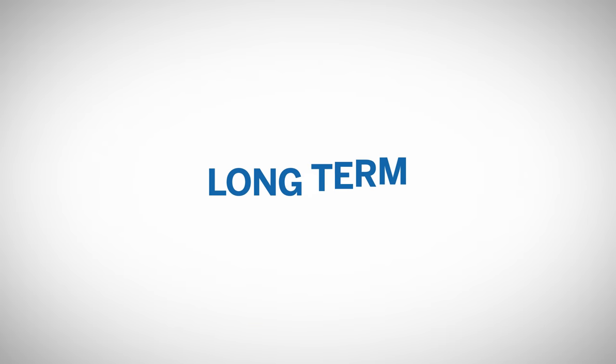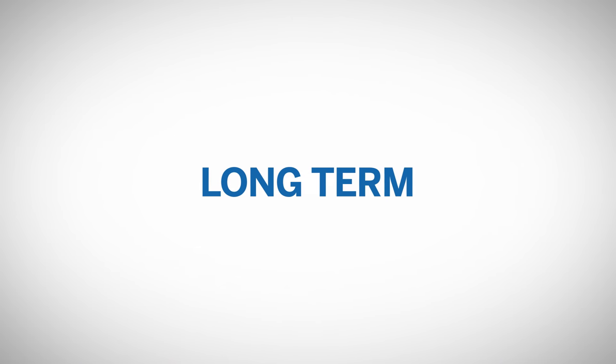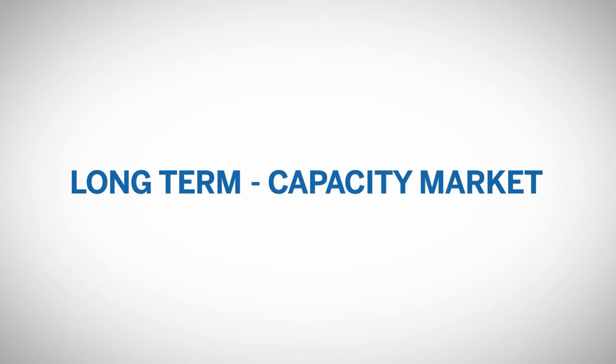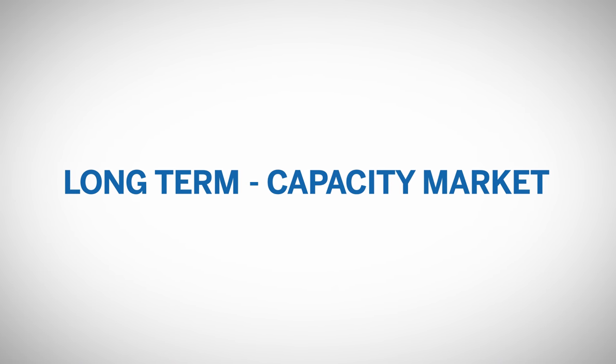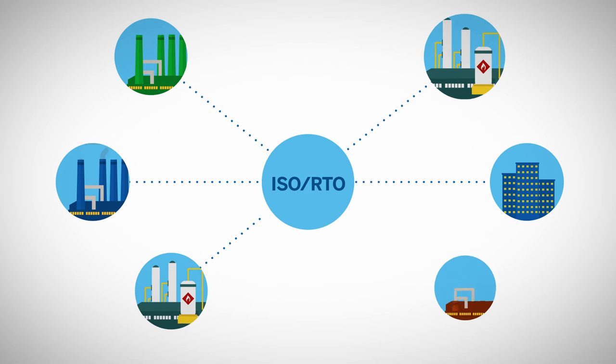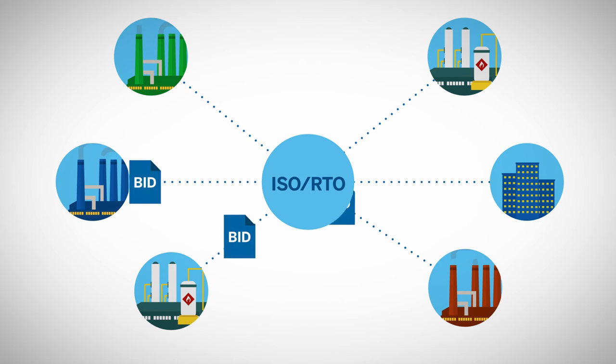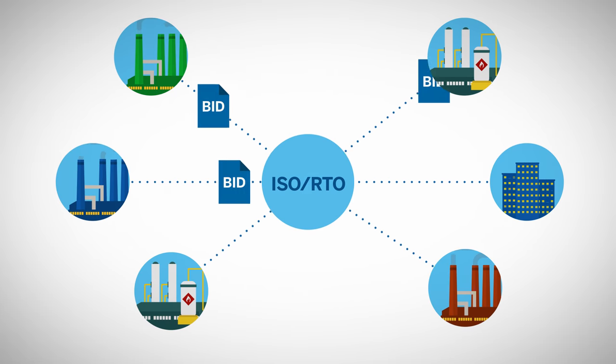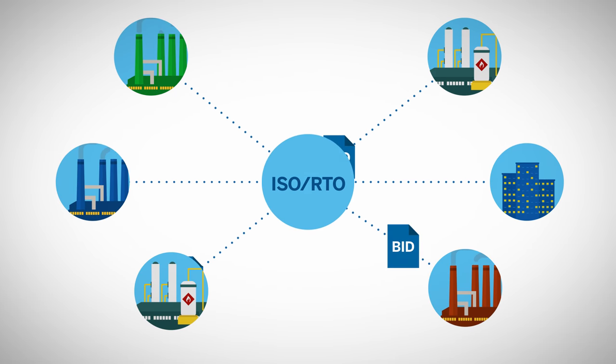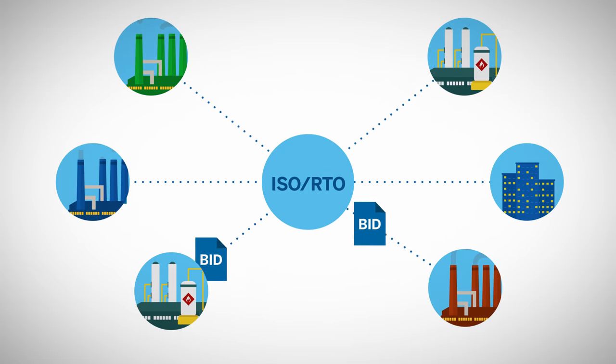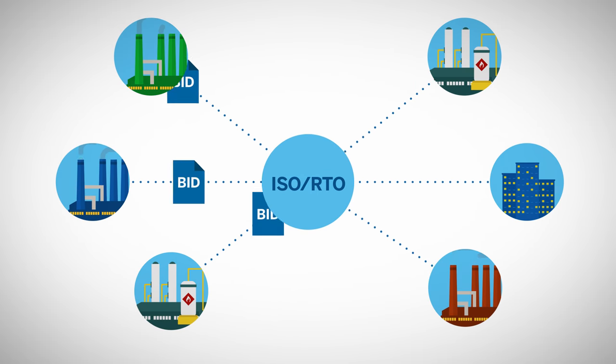For longer-term grid resource stability, ISOs and RTOs operate a capacity market that auctions the commitment of providing electricity generation capacity to ensure generation exceeds load in the long term. This market incentivizes long-term capital investment in generation resources, and revenues are paid to the capacity providers regardless of whether energy is produced or not.